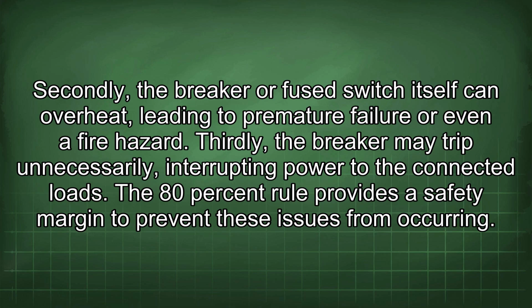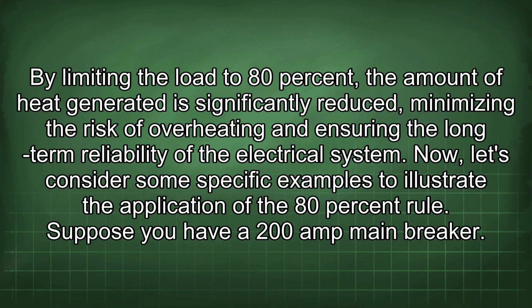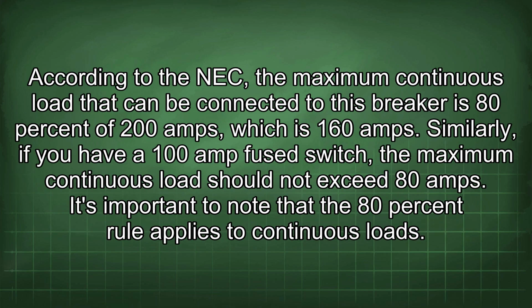The 80% rule provides a safety margin to prevent these issues from occurring. By limiting the load to 80%, the amount of heat generated is significantly reduced, minimizing the risk of overheating and ensuring the long-term reliability of the electrical system. Now let's consider some specific examples to illustrate the application of the 80% rule. Suppose you have a 200 amp main breaker. According to the NEC, the maximum continuous load that can be connected to this breaker is 80% of 200 amps, which is 160 amps.